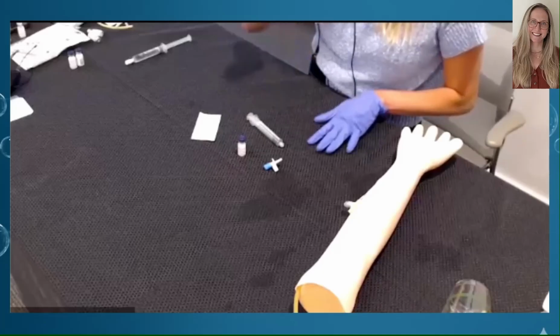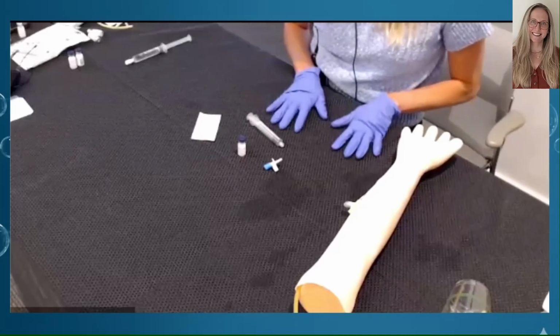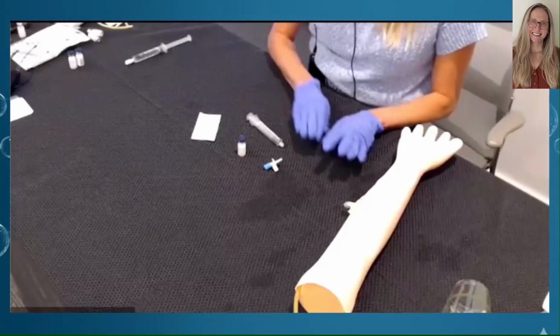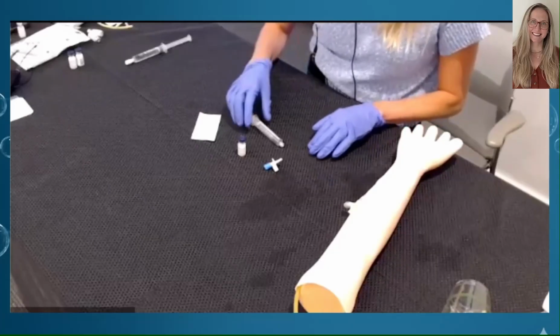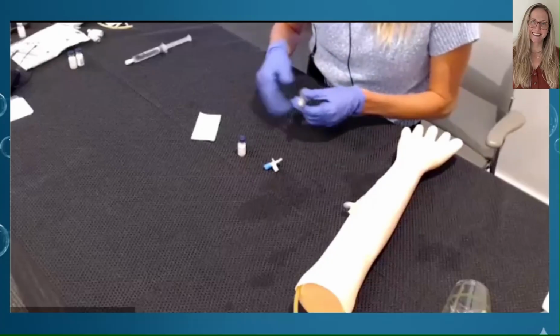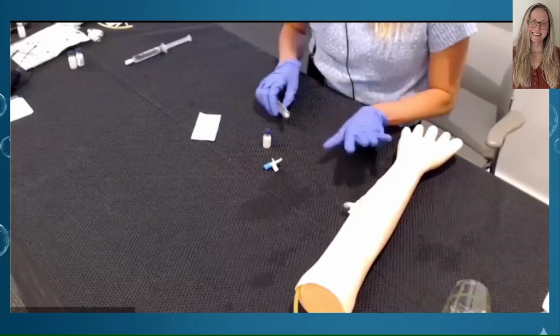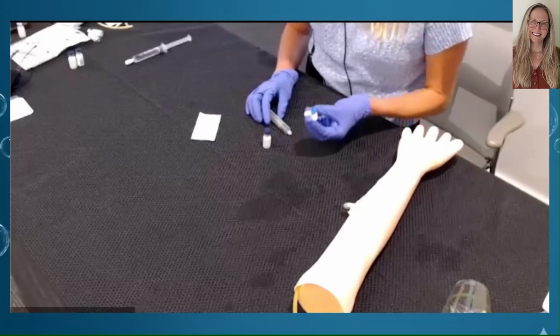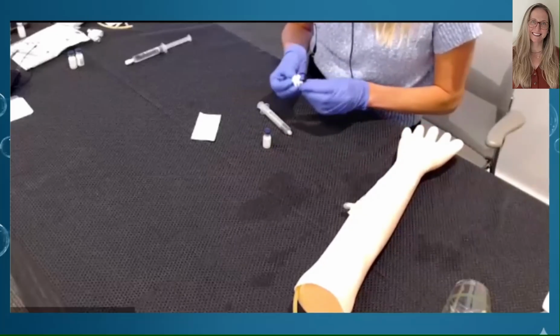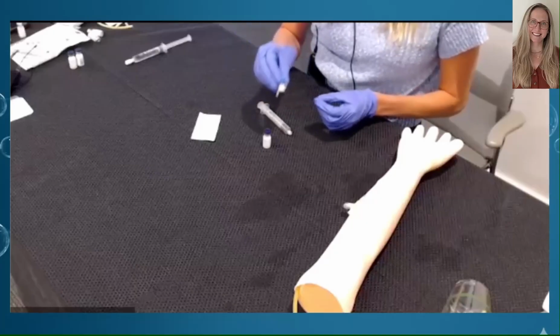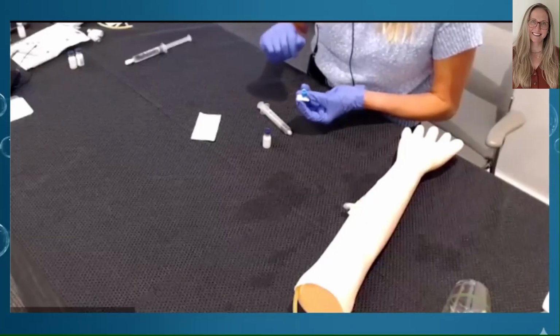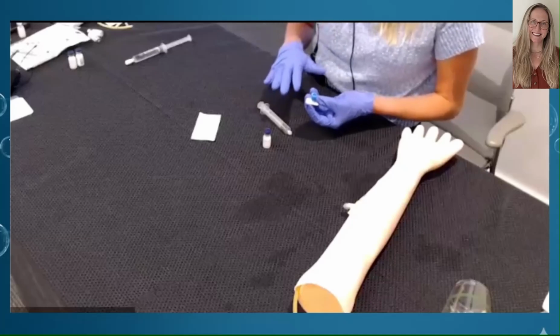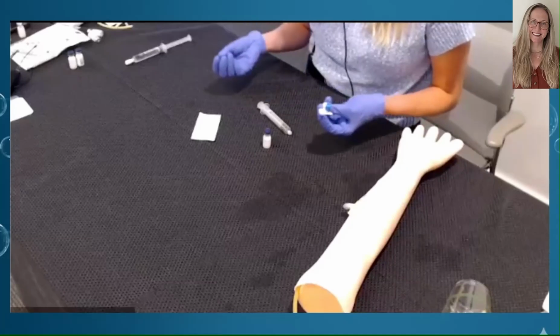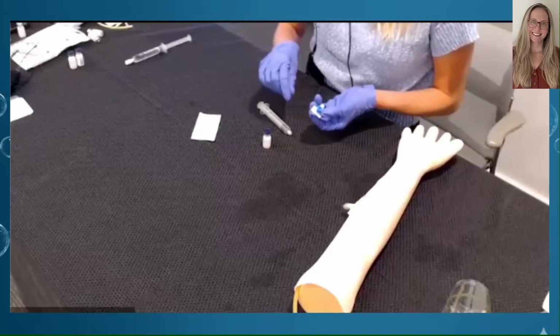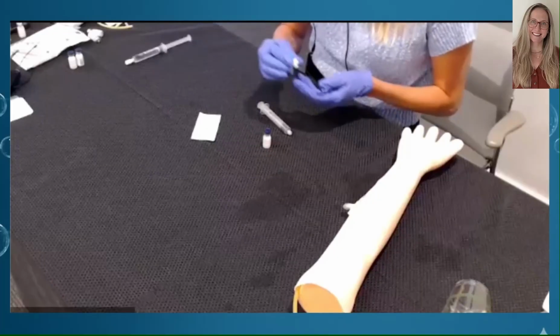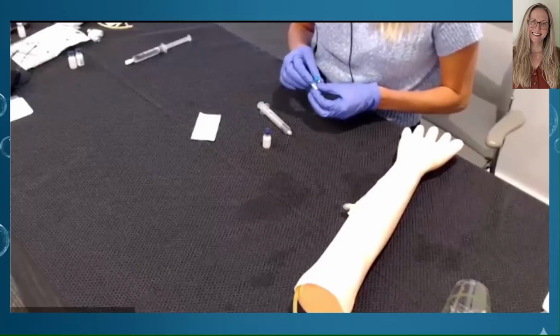Now, there's two methods that you can use to administer the contrast for cardiology. So the first is a direct bolus method. And for this one, we're just going to take an empty syringe and withdraw the contents of the Optison vial and then inject it directly. We do have a vent spike here that is available from the manufacturer. This spike not only simultaneously vents, but then you could also pull out the contents with it. The other alternative is if you had a needle, you could also just use a standard needle to vent it and then use a second one to withdraw it as well. But we have 2-in-1 here, so we're just going to use it for this demonstration.